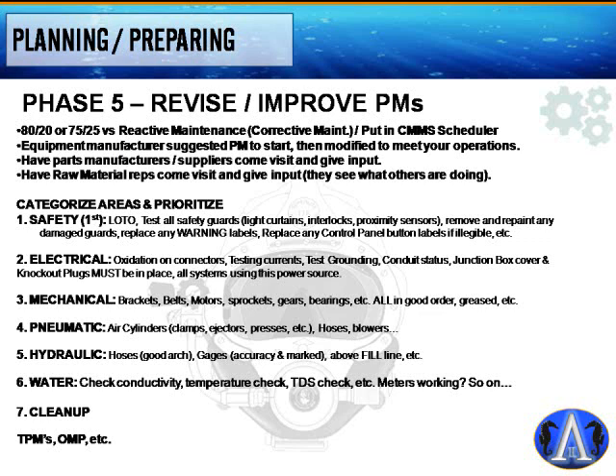Electrical PMs include checking for oxidation on connectors (common in humid environments), testing currents and grounding, confirming conduit status, and ensuring junction box covers and knockout plugs are in place — another OSHA requirement. Mechanical PMs cover brackets, belts, motors, sprockets, gears, bearings, and lubrication. Technicians should carry a testing bag for tasks like checking airflow in ducts, fans, and dust collectors. Thermal imaging is very useful here.